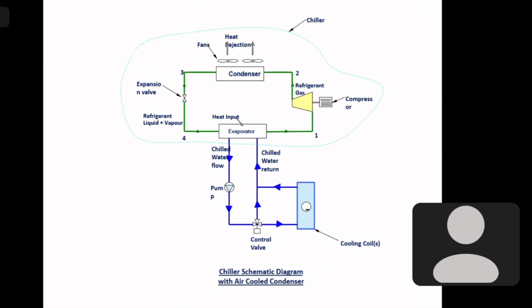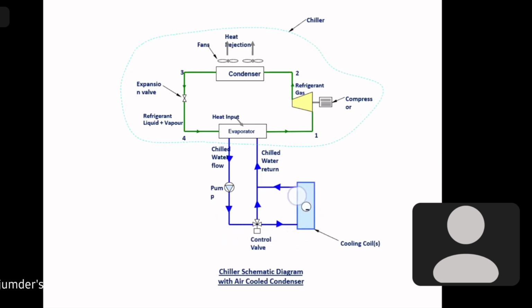Here everything is the same, but it's an air-cooled chilled water system. Here you have the compressor, the air-cooled condenser, the refrigerant gas, and the expansion valve, which expands the refrigerant coming out from the condenser, but it's not directly fed into the cooling coil. It goes to another heat exchanger, a shell and tube kind of heat exchanger, which is called the evaporator here. Here the refrigerant is expanded and we cool water in that evaporator. And we take that cold water to the room where we need to cool, and there we pass the cold water through a cooling coil and then pass the return air from the room over that cooling coil to recool it and supply it back to the room.